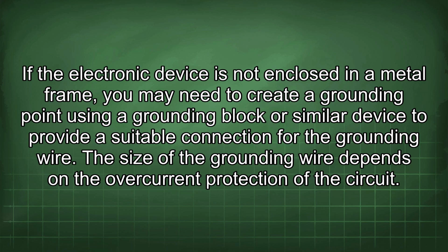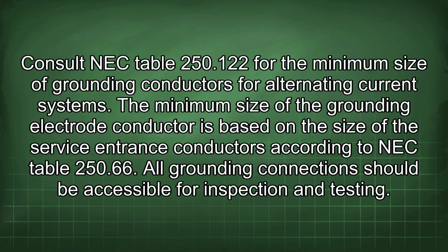The size of the grounding wire depends on the overcurrent protection of the circuit. Consult NEC Table 250.122 for the minimum size of grounding conductors for alternating current systems. The minimum size of the grounding electrode conductor is based on the size of the service entrance conductors according to NEC Table 250.66. All grounding connections should be accessible for inspection and testing.